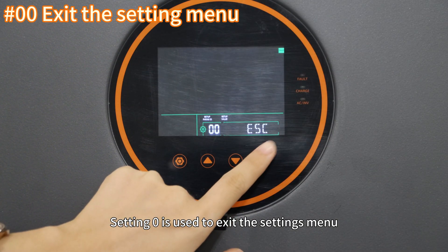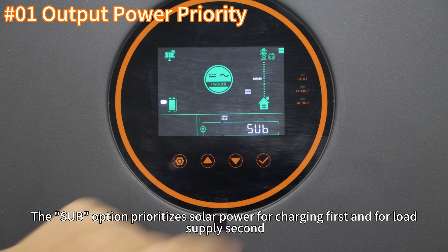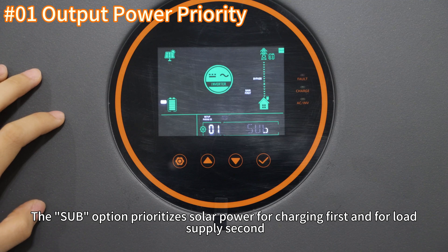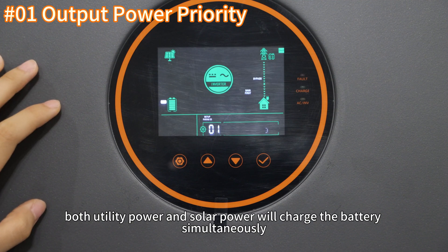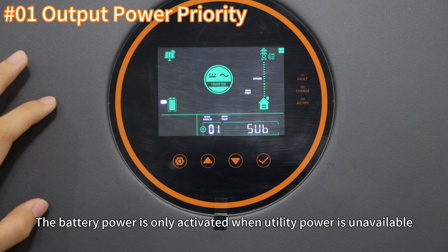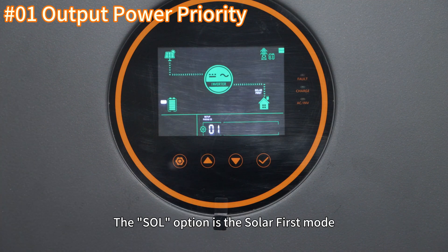Setting 0 is used to exit the settings menu. Setting 1 is for configuring power priority. The SUB option prioritizes solar power for charging first and for load supply second. If solar energy is insufficient, both utility power and solar power will charge the battery simultaneously, with excess utility power used to support the load. Battery power is only activated when utility power is unavailable.